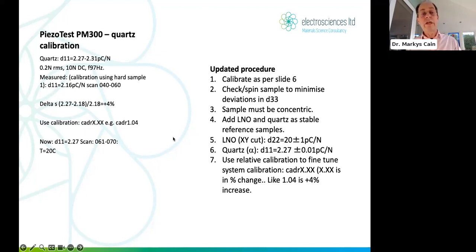Well, what you can do is you can use a certain calibration parameter on these machines called CADR relative. This is how you do it. It's also how you do it for lithium niobate. When you have any standard reference sample where the d33 is less than 100, okay, you have to use this relative calibration to fine-tune the system calibration. So if, for example, the machine gives you a 4% error, then you have to recalibrate at 1.04. You have to go CADR 1.04, and that will then give you your 4% recalibration, because you're using quartz and you know quartz, you put it in your machine and you've now calibrated it on that day, at that time, at that frequency, at that preload to quartz.